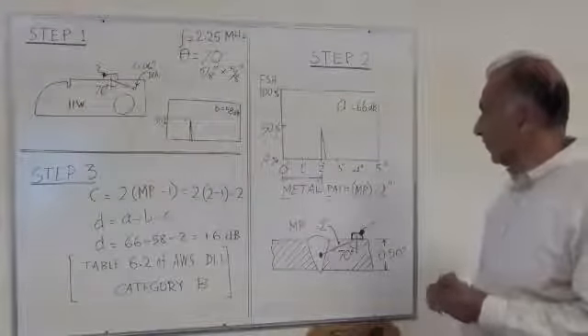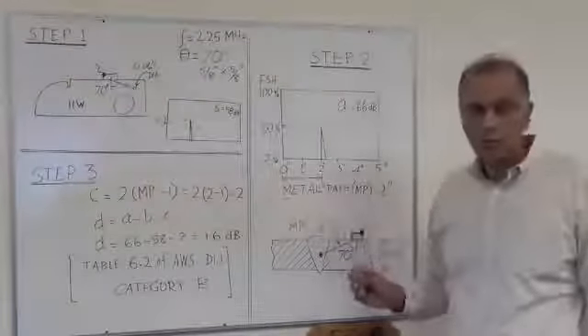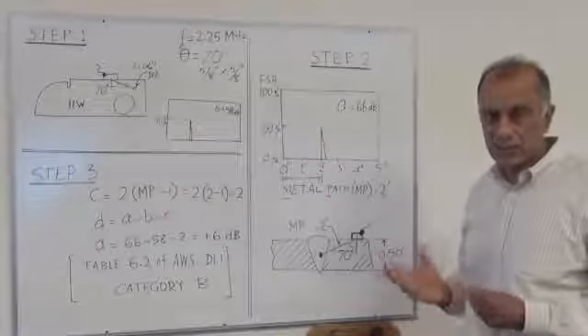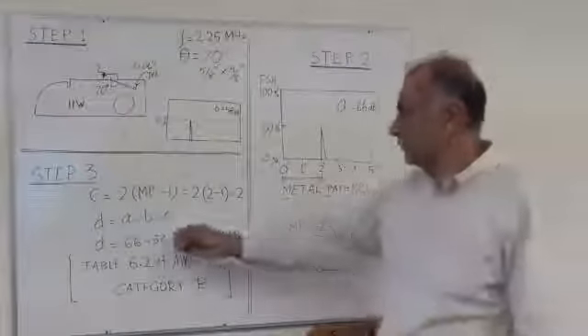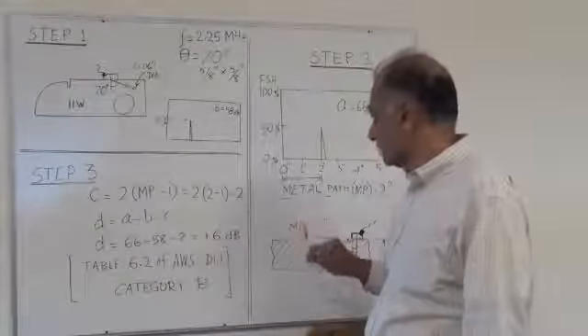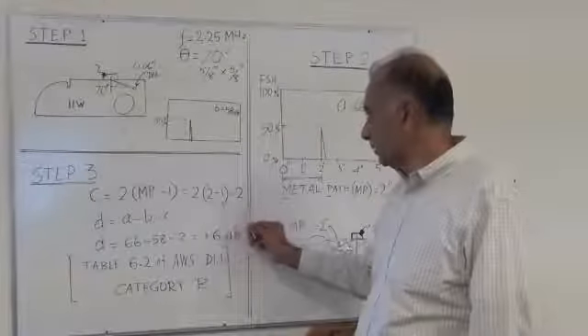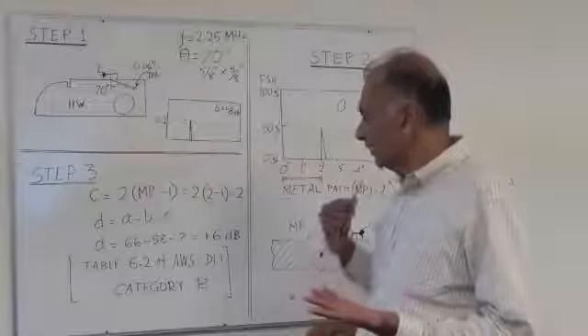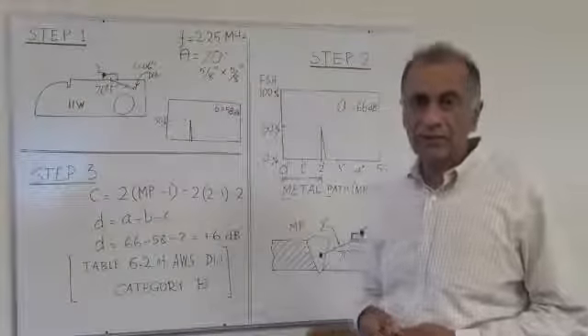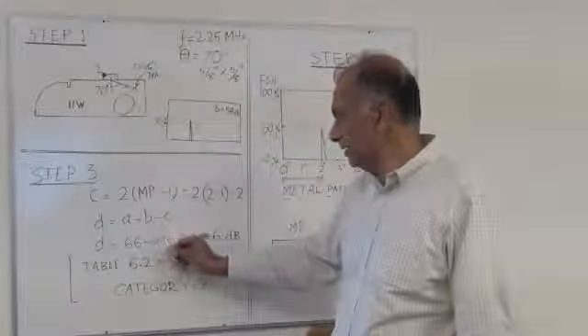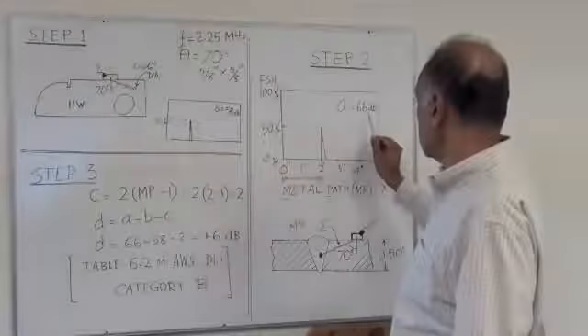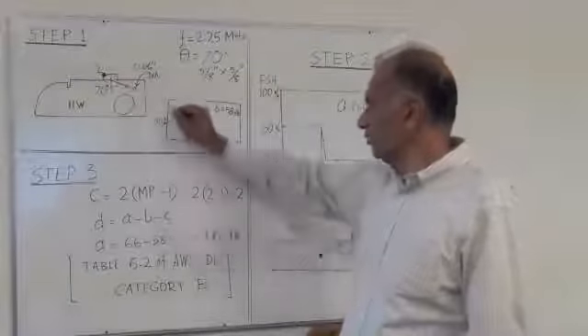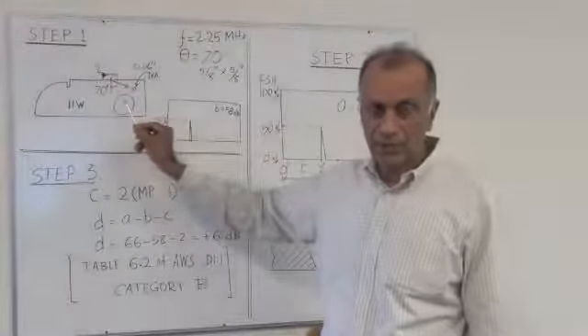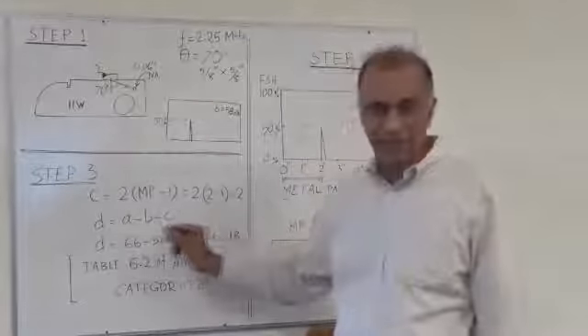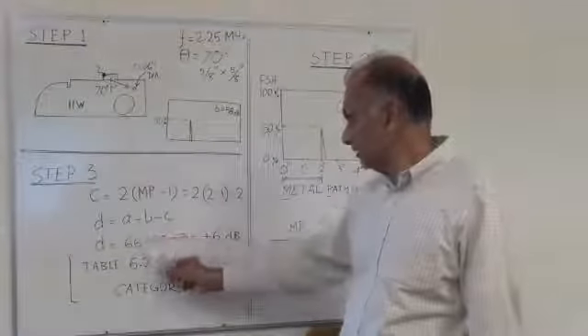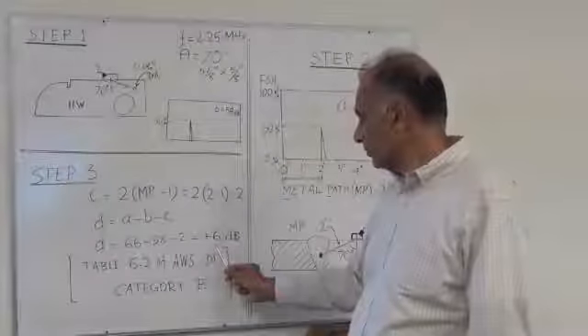Now when we find the indication, we also measure the metal path to calculate the attenuation factor, which is C. So the attenuation factor C is given by 2 times (metal path minus 1). So let's assume the metal path is 2 inches, so 2 times (2 minus 1) equals 2. Now using A, B and C, we calculate D, and D equals A minus B minus C. So in this case, A equals 66 dB on the indication, B equals 58 dBs on the 0.06 inch hole, and C is the attenuation factor, which is equal to 2. So A minus B minus C, which is 66 minus 58 minus 2, equals plus 6 dB.